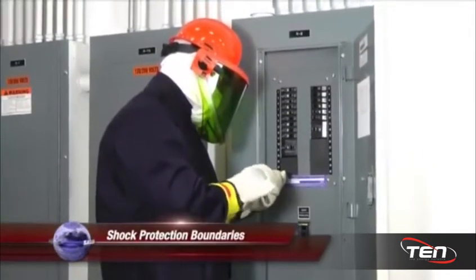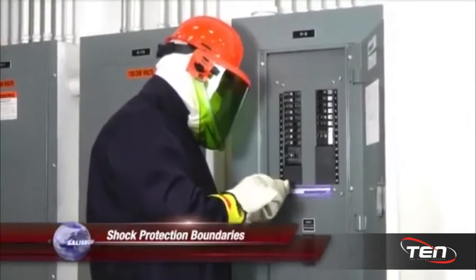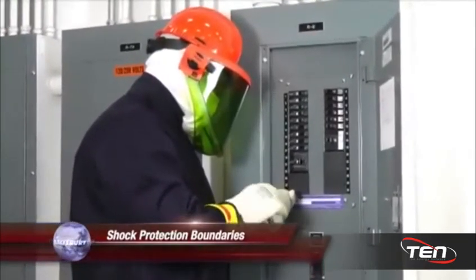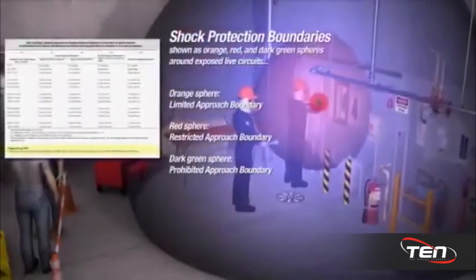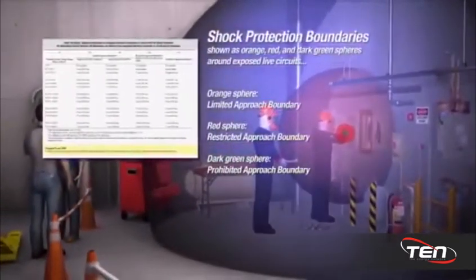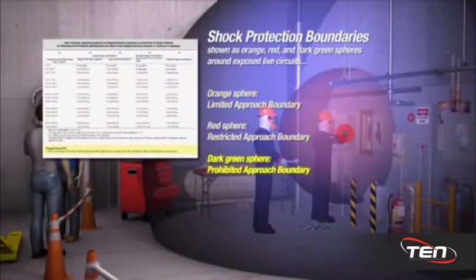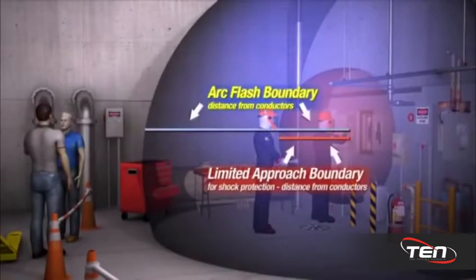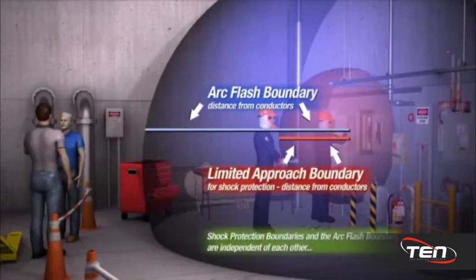Shock protection boundaries function in the same way to protect workers from exposure to dangerous energized conductors. As seen in Table 130.4(c) and the illustrations, there are specified boundaries for limited, restricted, and prohibited approach. The arc flash boundary might be a greater distance from the energized electrical conductors or circuit parts than the limited approach boundary for shock protection. The shock protection boundaries and the arc flash boundary are independent of each other.